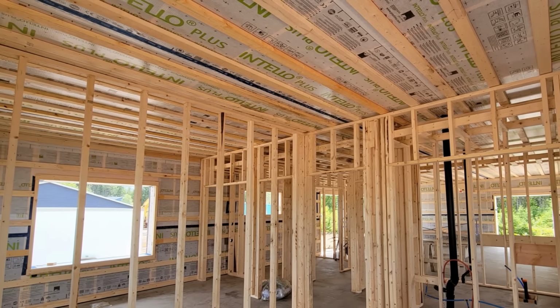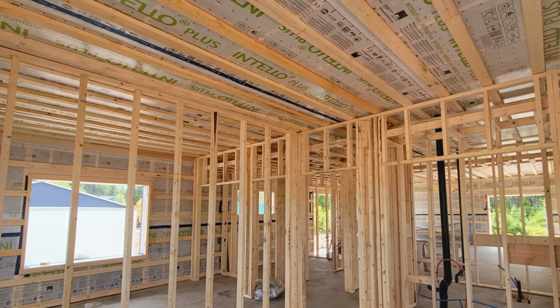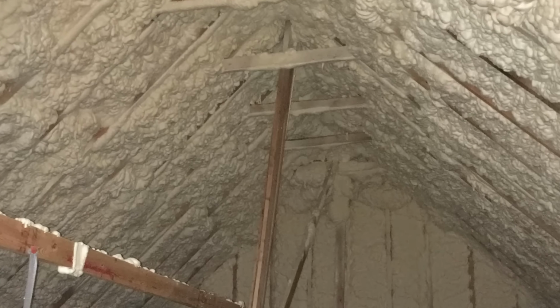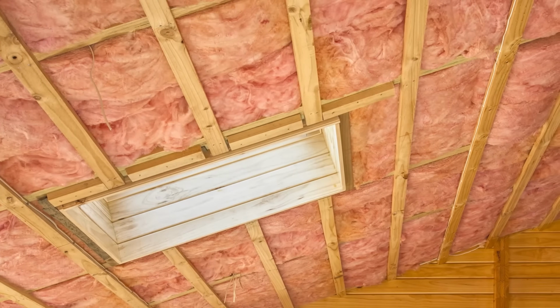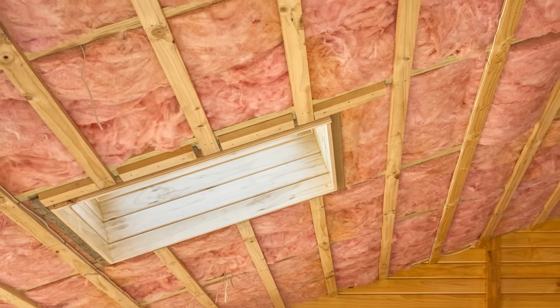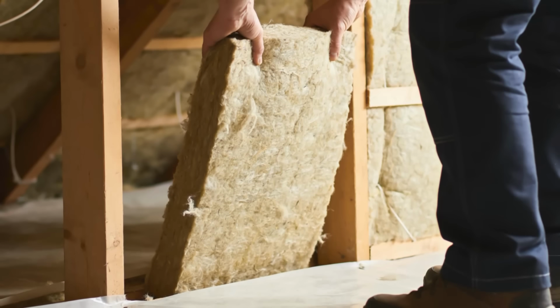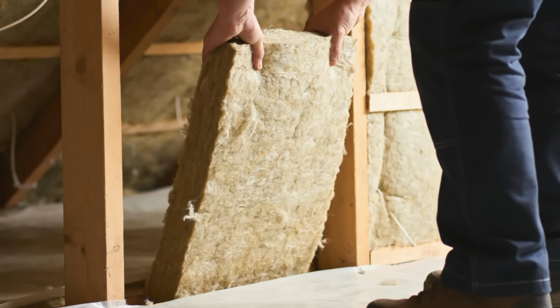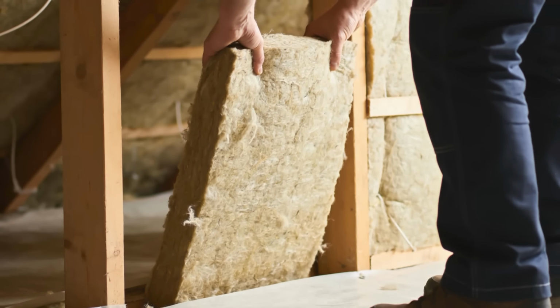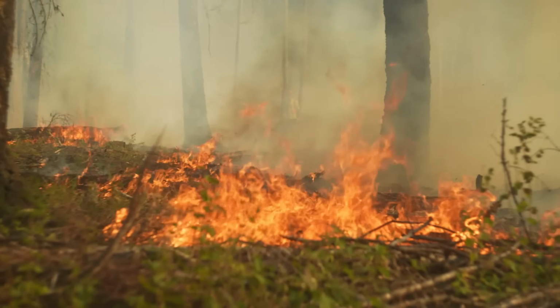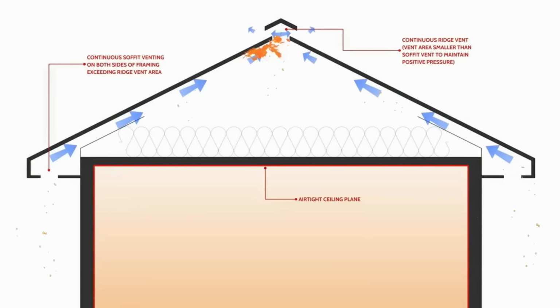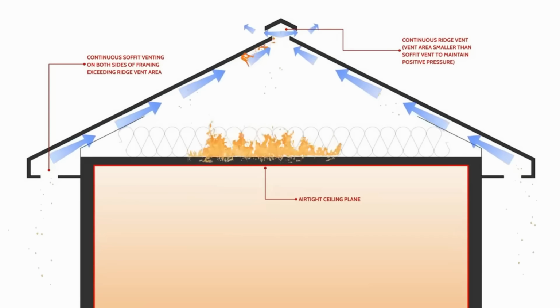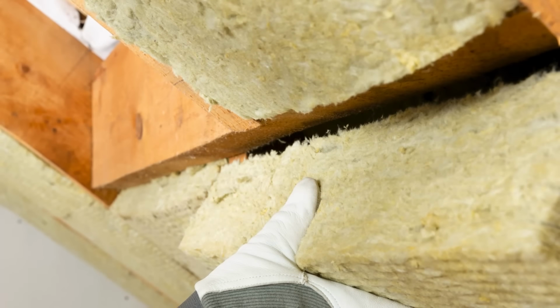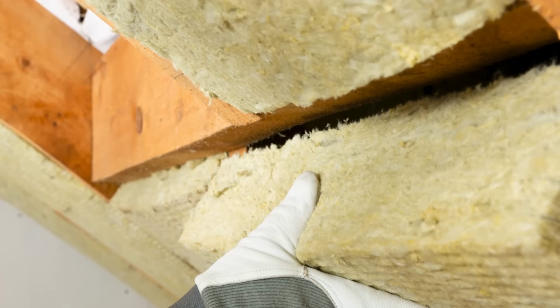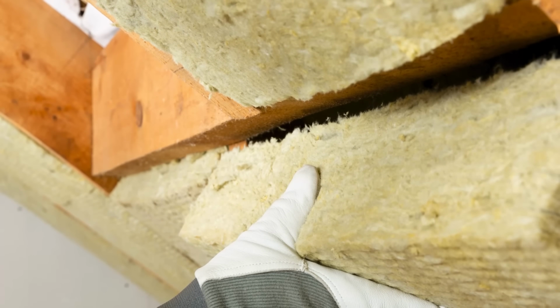By moving your air and thermal control layers from the flat ceiling plane to the surface of the roof sheathing or roof deck, you bring the entire attic space and all your ductwork completely inside the home's conditioned boundary. This protects the equipment from extreme temperatures, prevents condensation on the ductwork, and improves indoor air quality. Not to mention it's extremely beneficial in preventing embers from entering the attic through the vents if you're in a wildfire-prone area.